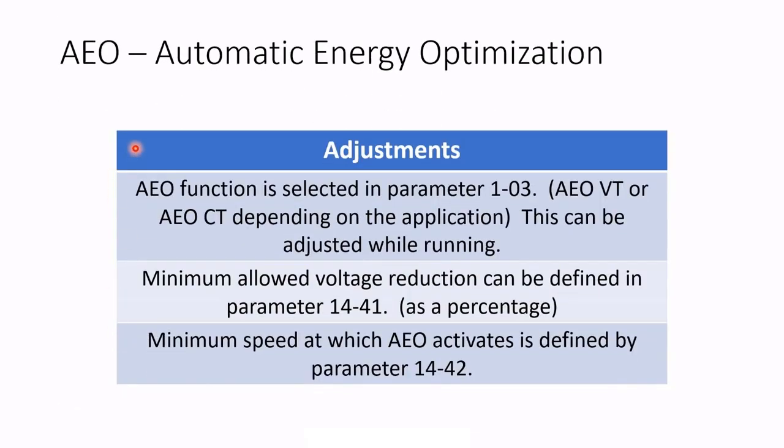Parameter adjustments: the AEO function is selected in parameter 103. There are two choices — AEO variable torque or AEO constant torque. Choose the right one for your application. This can be turned on and off while the drive is running.